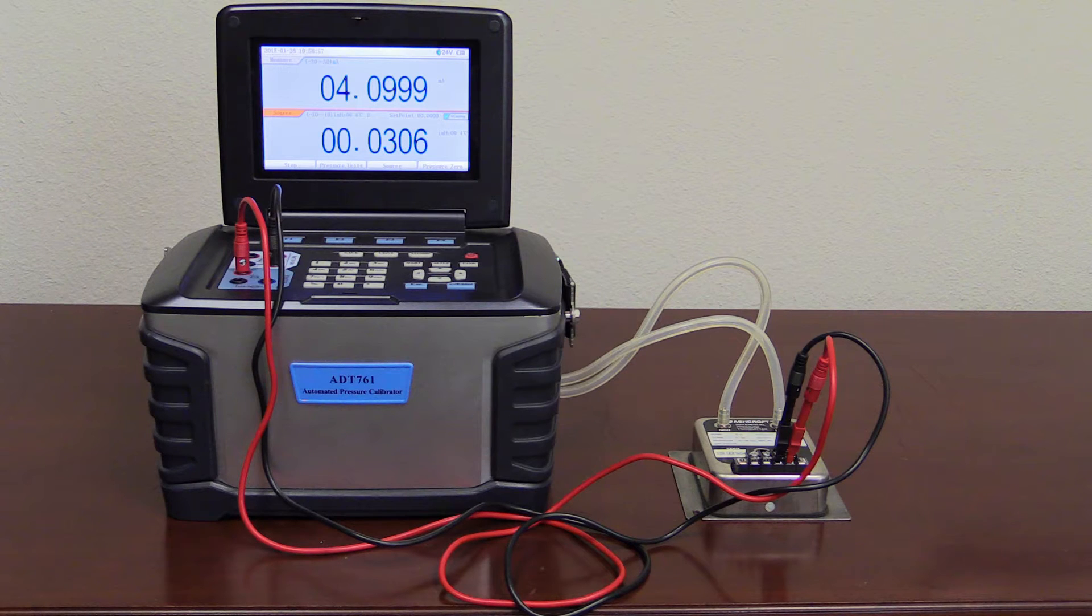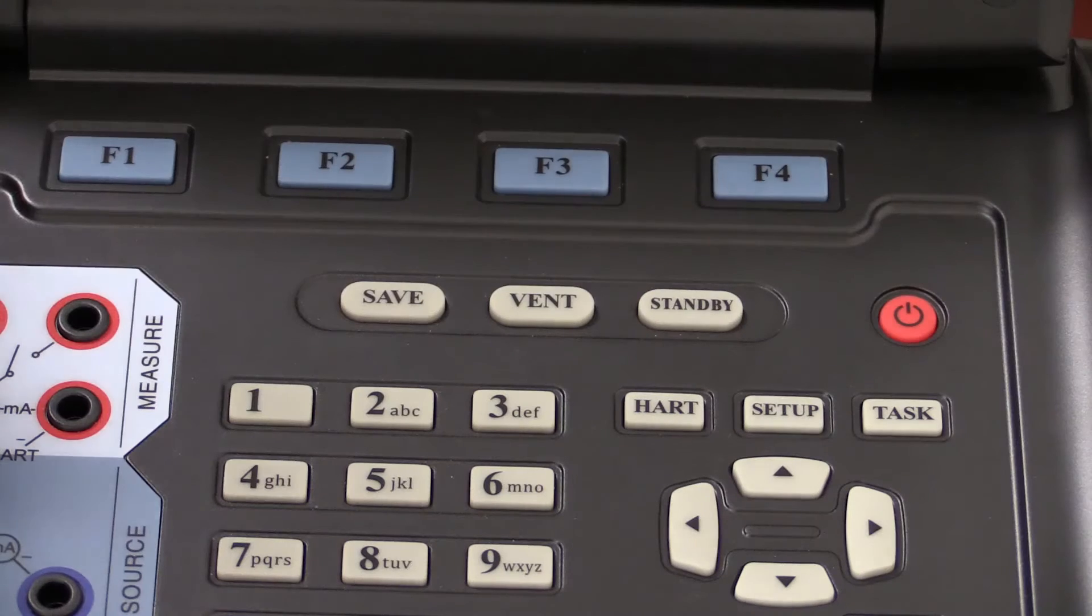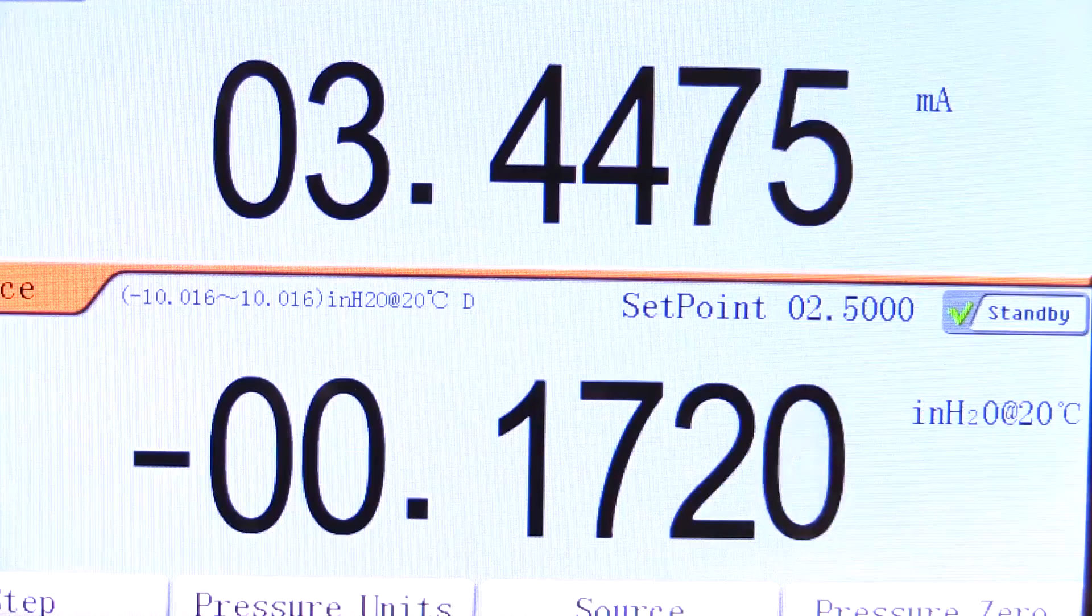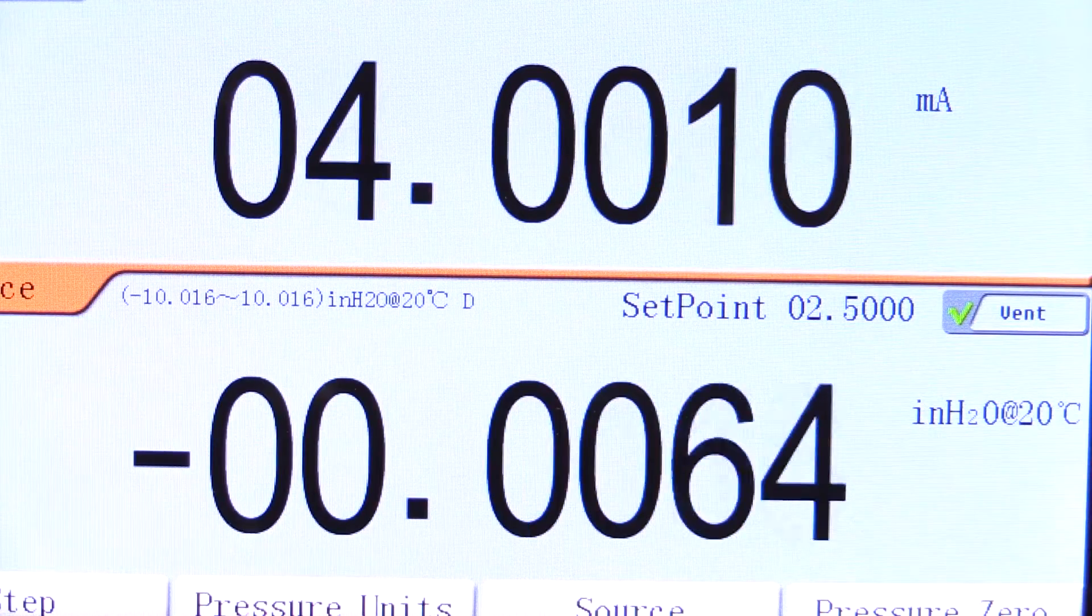For this calibration, we will perform a 3-point test at 0, 2.5, and 5 inches of water. The first step is to vent to atmosphere and record the zero point.